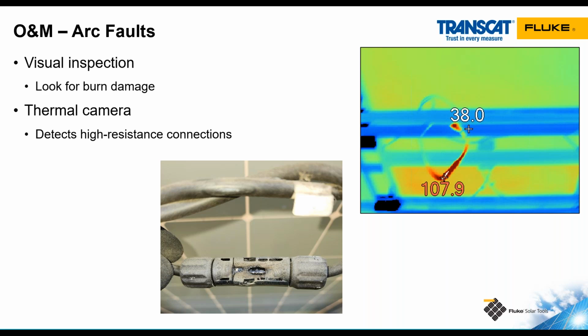Here we've got 2 pictures of a module interconnector that was damaged. The one on the top right is a thermal image where that connector is at a higher temperature than other connectors in this system. On this bottom one, there's a little gap between the positive and negative sides of this connector, so I'm assuming they didn't plug it in all the way. I believe that heated up, and then you had this metal part here making a connection through this burnt out wire, and that series arc fault becomes a parallel arc fault as well. So you get both situations in this example.